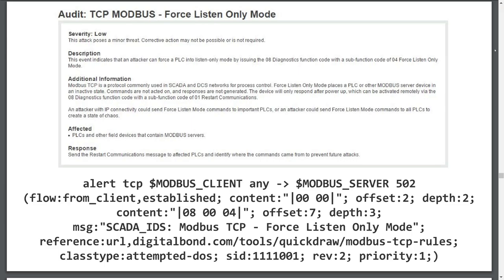The any following the variables represents the TCP source port. We see the direction arrow, meaning these packets are coming from a TCP Modbus client and are being sent to another variable, which is the Modbus server or slaves listening on TCP port 502. I will quickly skip over the rest just to get the erroneous fields out of the way.